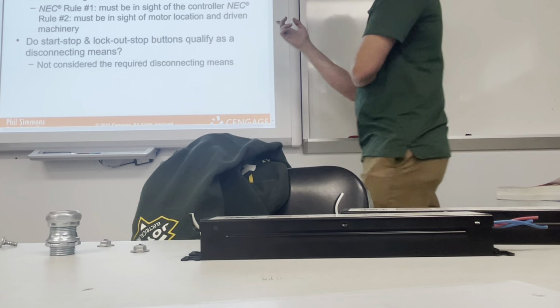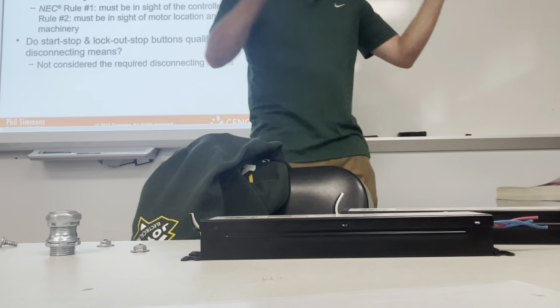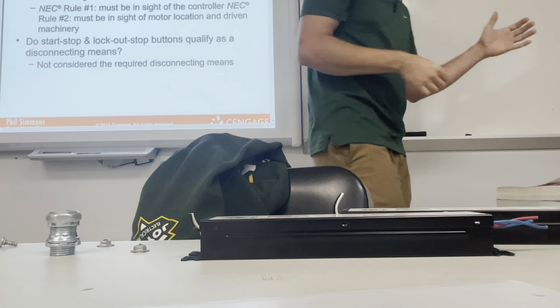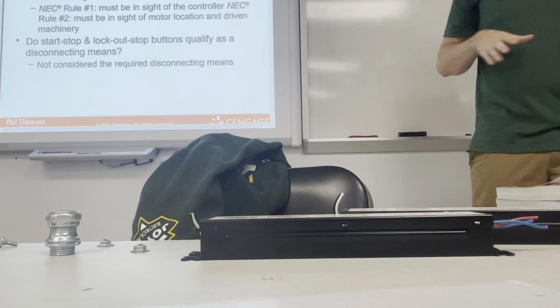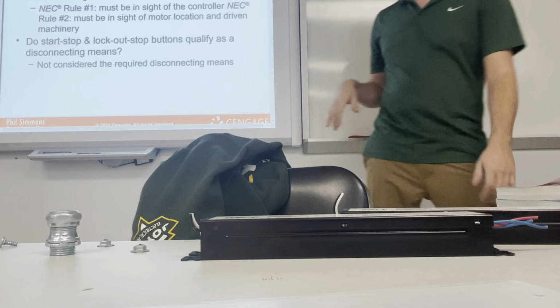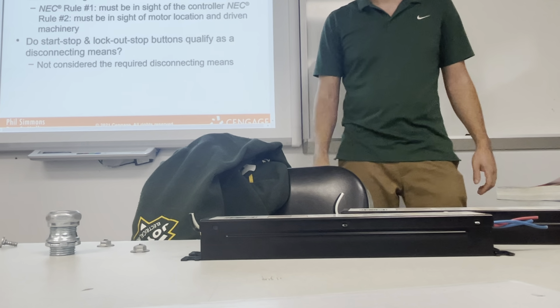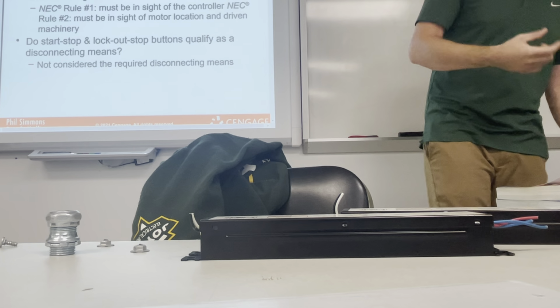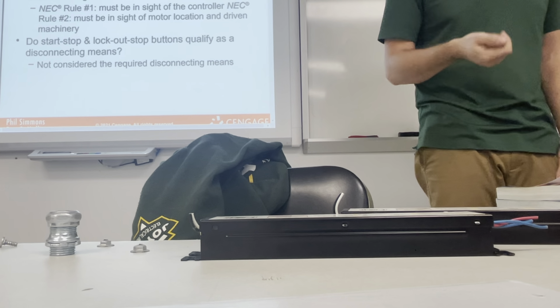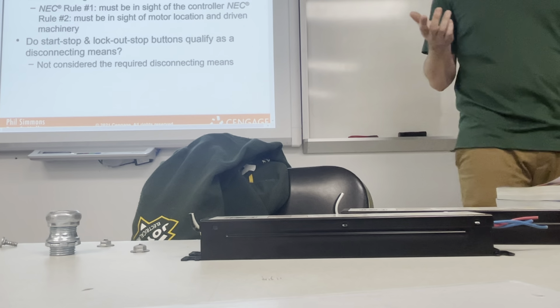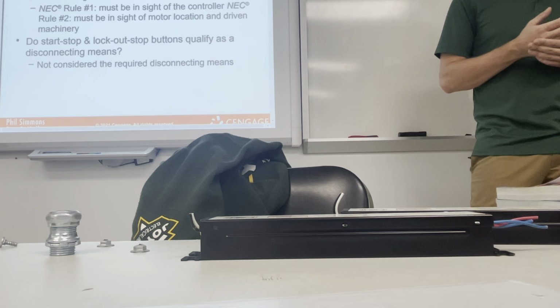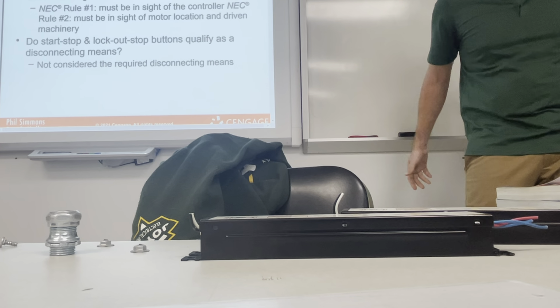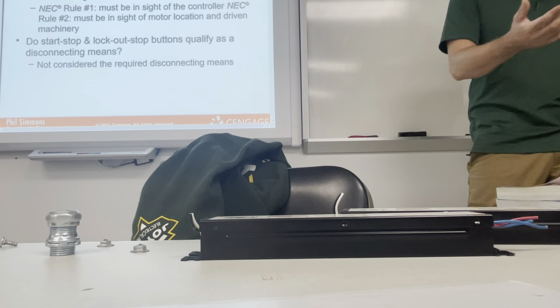So what do they mean by disconnect? Obviously like a big disconnecting thing, little lever action, nice and firm, turns that motor off, everybody feels nice and safe. What they mean with the lockout tagout is, yes, would the lockout tagout prevent the circuit from being energized, from being turned on? Yes, but only usually the control side. You gotta make sure that that disconnect, what's supplying that motor with 3-phase power, is in fact killed.